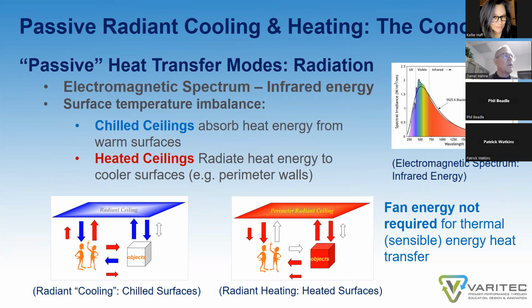Let's look at radiation. Radiation is energy heat transfer in the form of the electromagnetic spectrum. We all experience it every day we walk outside and are exposed to the sun. It is infrared energy specifically that we're dealing with. And we actually use radiant heat transfer by creating an imbalance of energy of surfaces within a space. We either chill the ceilings to absorb heat energy from surfaces in a space, or heat ceilings or walls perhaps, in order to add radiant energy to a space. When you use this mode of heat transfer, fan energy is not required to move energy. It is by creating an imbalance of energy levels within the local zone, within the space, that allows heat transfer to occur.